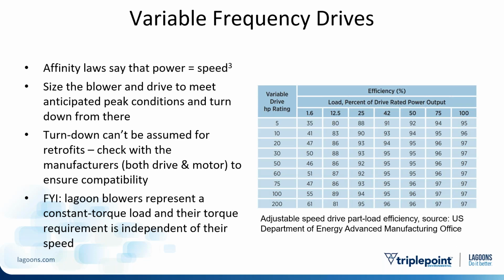But with retrofits, you cannot assume that you can automatically turn down a motor. It's really important to check with the manufacturers, both the drive and the motor, to ensure complete compatibility and make sure that you really can accomplish what you're trying to accomplish. It may be that the better bet is to leave that older blower as a single speed, just let it run constant speed exactly where it's set. And if that's a good bit over where you need to be, maybe you can resheave it and reduce your flow that way a little bit, maybe save a little energy there.